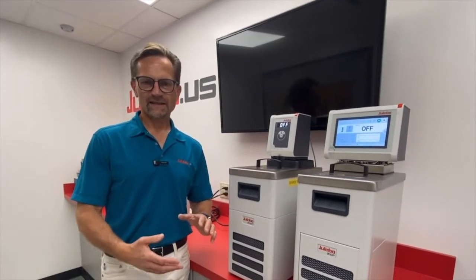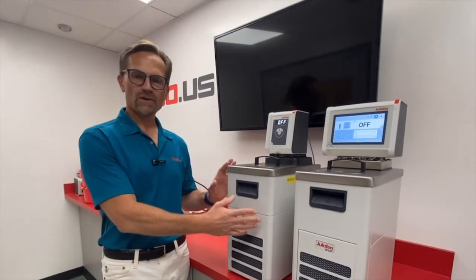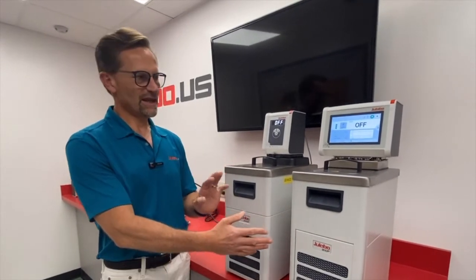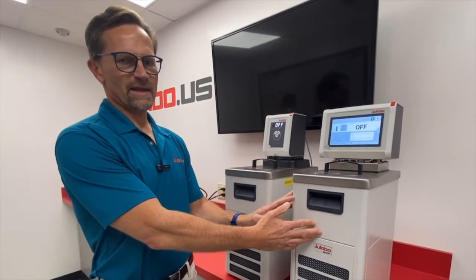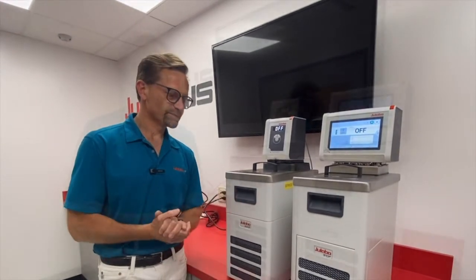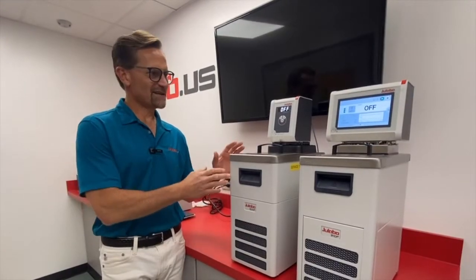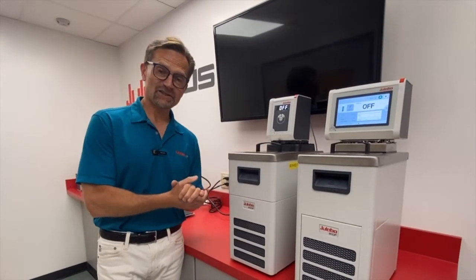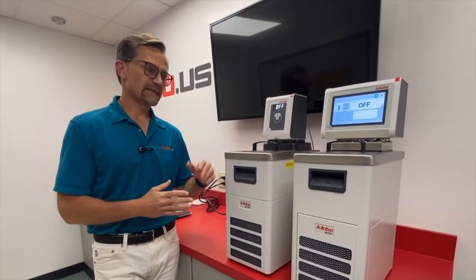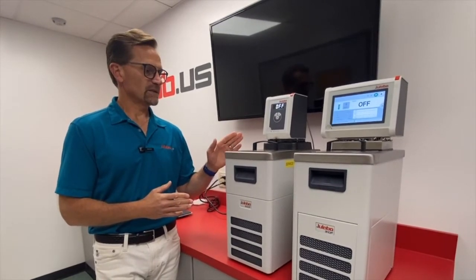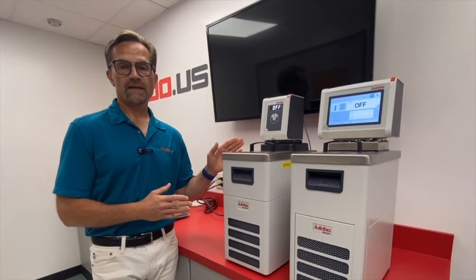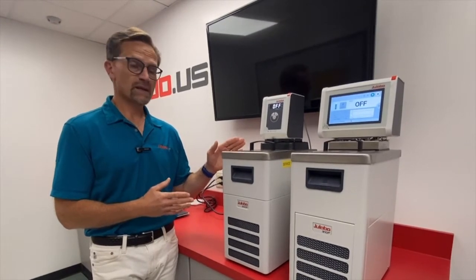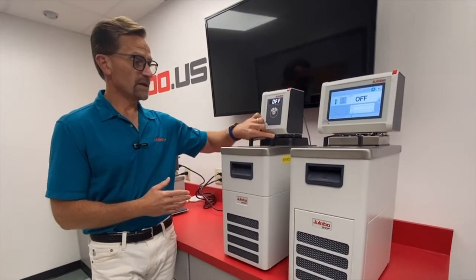In this video I'd like to discuss the differences between the CORIO CD models and the MAGIO MS and MX models. The CORIO CD can come in heating circulator combinations with 1 or 2 kilowatt heaters up to 150 degrees C. It has a single speed pump up to 16 liters per minute and 5.1 psi. The only adjustability with the pump is the flow diverter.